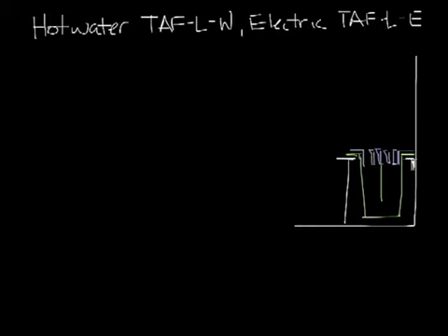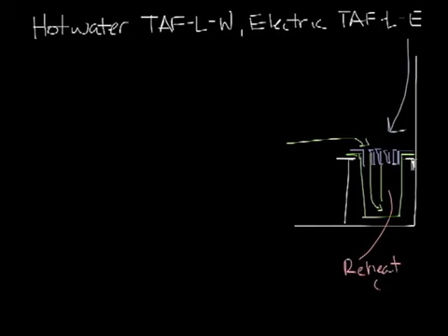Let's draw that in. Now the way this works, the cold air will fall off the perimeter glass. That will induce room air into the front, and everything will fall to the bottom of the plenum. Now the reheat coil is down here, so as the air passes over it, the air will warm up and rise. And that's how you would handle the perimeter heating. So now let's bring in a video of a test we did with the TAF-L heating unit.